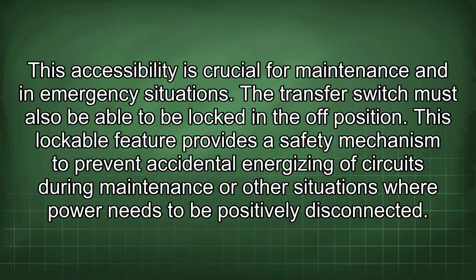The transfer switch must also be able to be locked in the off position. This lockable feature provides a safety mechanism to prevent accidental energizing of circuits during maintenance or other situations where power needs to be positively disconnected.